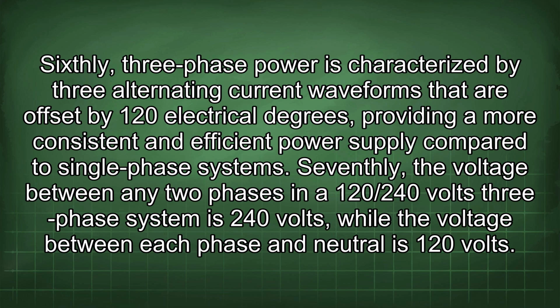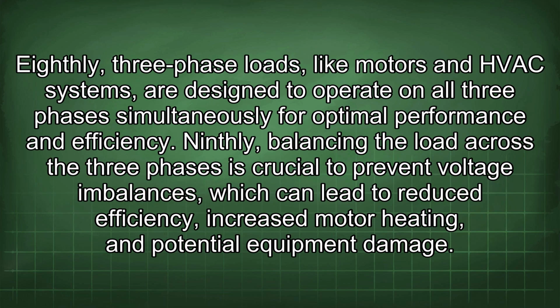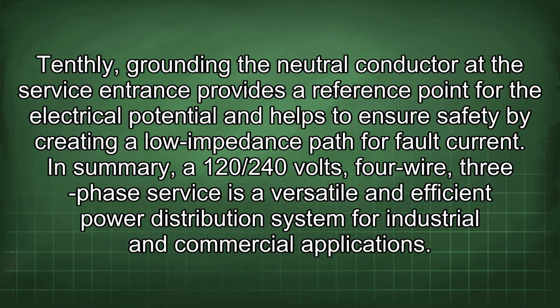Seventhly, the voltage between any two phases in a 120/240 volts three-phase system is 240 volts, while the voltage between each phase and neutral is 120 volts. Eighthly, three-phase loads, like motors and HVAC systems, are designed to operate on all three phases simultaneously for optimal performance and efficiency. Ninthly, balancing the load across the three phases is crucial to prevent voltage imbalances, which can lead to reduced efficiency, increased motor heating, and potential equipment damage. Tenthly, grounding the neutral conductor at the service entrance provides a reference point for the electrical potential and helps to ensure safety by creating a low impedance path for fault current.